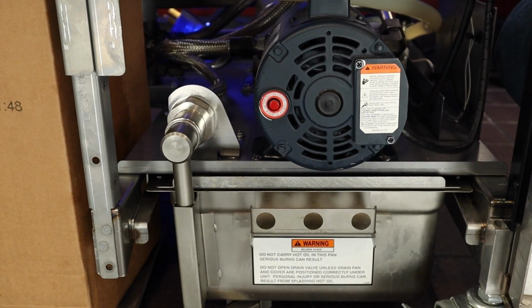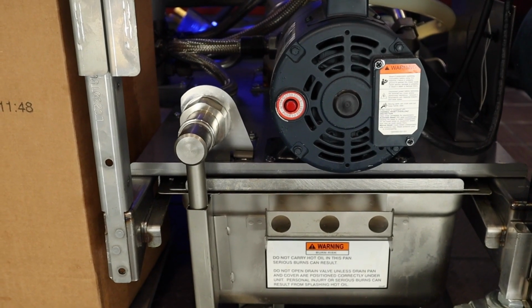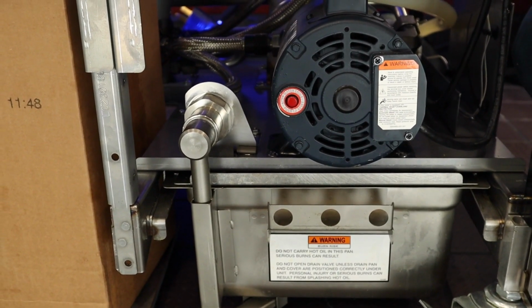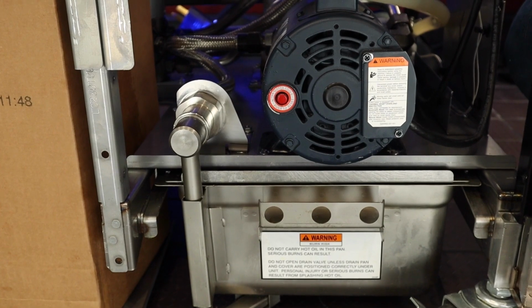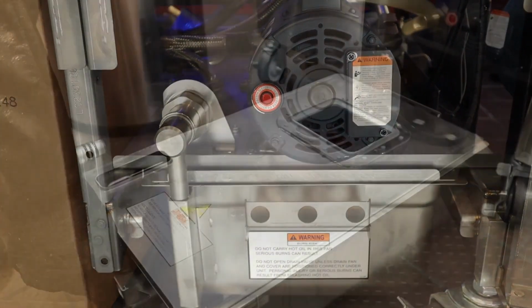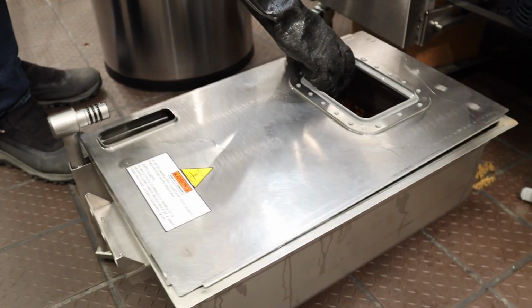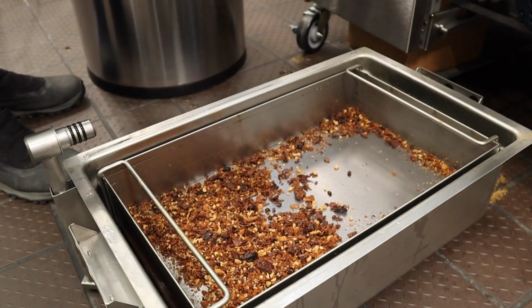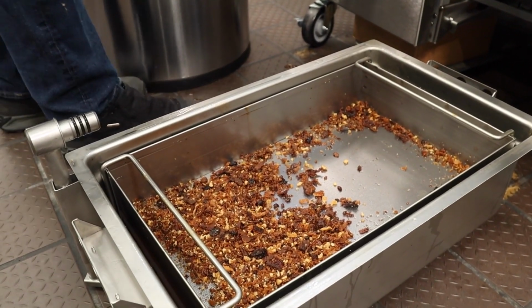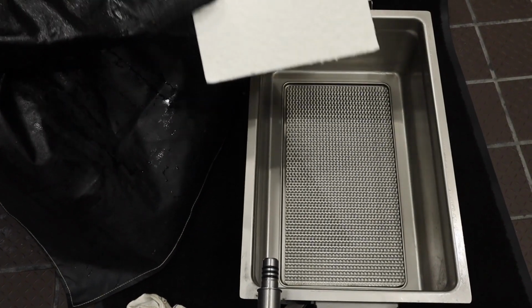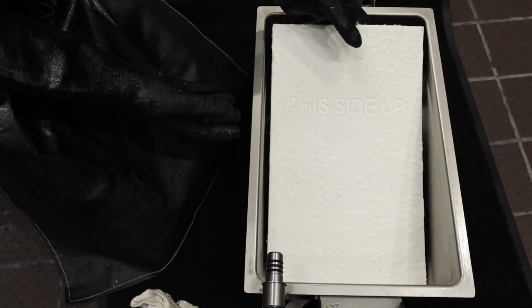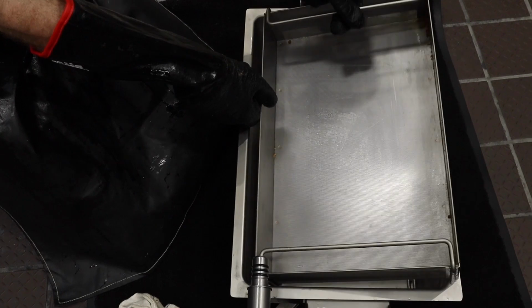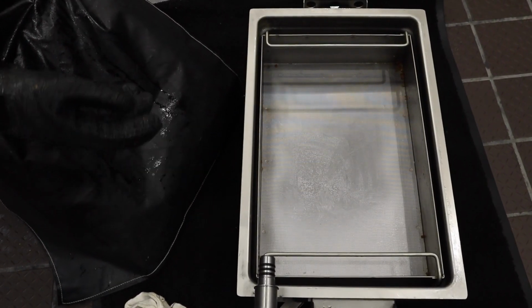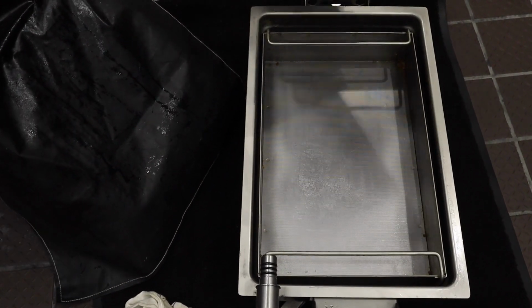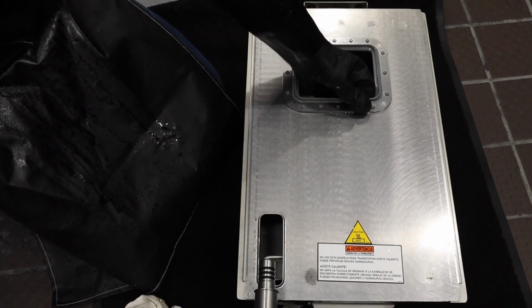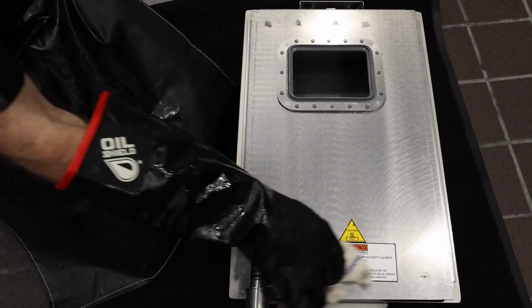Something to keep in mind is if it was just the thermal overload that was tripped, we need to make sure that we take this opportunity to train the store staff, because more often than not, this is caused by heavy crumb buildup on the filter pad inside the filter pan. And this is an operational issue. Make sure to remind them that the filter pad needs changed once a day, and that if they are a high volume store, they may need to scrape the crumbs off the top of the filter pad in the middle of the day to maintain filtration performance. They just have to be careful not to puncture the pad when doing so.